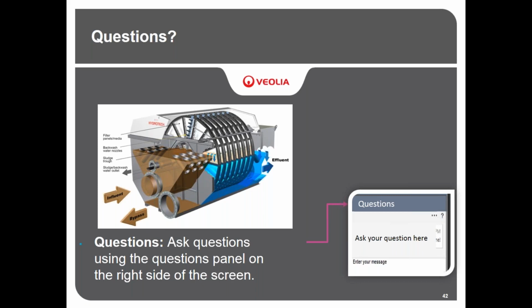Okay. Another question that we have has to do with fouling. How can you prevent fouling on the media? We do this in a number of ways. Some of it is with chemical pretreatment. If you're able to stop it before it happens, that's ideal. Also, we do recommend chemical cleaning. There are chemical cleaning nozzles in the disc filter that you can install if you choose to, or you could do it manually, where the chemical cleaning system would hook up to the nozzle on the disc filter and spray the chemical onto the filter media, similar to the backwash but not as high of pressure, and then it can be rinsed off.